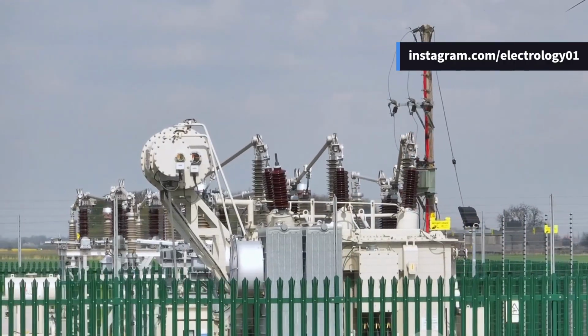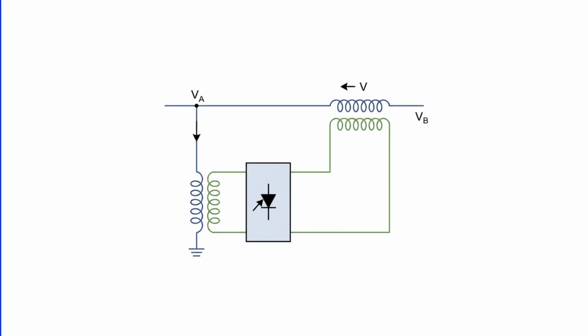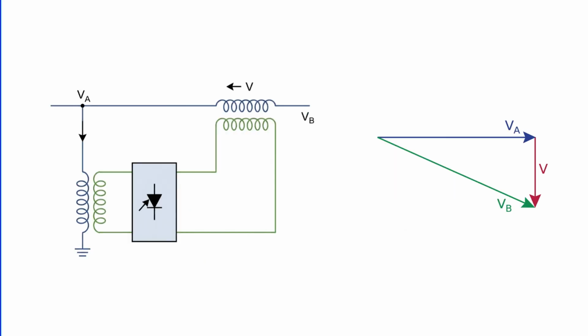Now we come to another fascinating FACTS device called the Thyristor controlled phase shifting transformer, also known as a phase angle regulator. This system consists mainly of a shunt transformer and a boosting transformer inserted directly into the transmission line. You can see the arrangement and phasor diagram on the screen. Let's break down the principle.